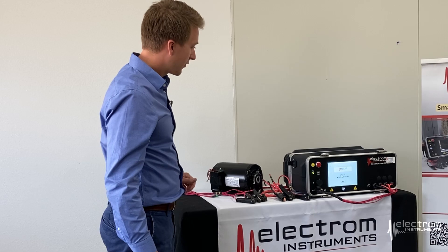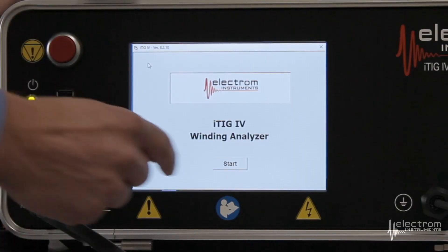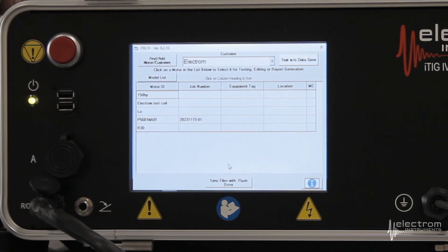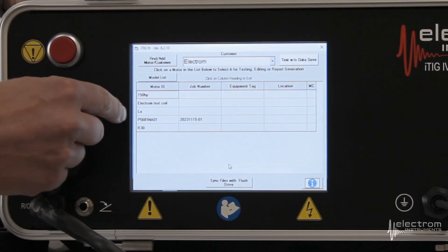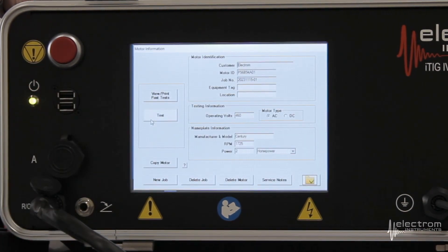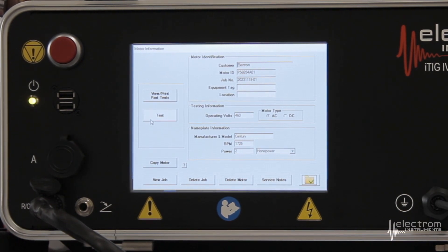The first step is on the instrument, you click Start. We see the customer directory or motor database. I have already entered our motor in the database, so we click the row containing our serial number. We now get the motor information, nameplate information and so on. As you can see, we already have most information typed in, including the job number.